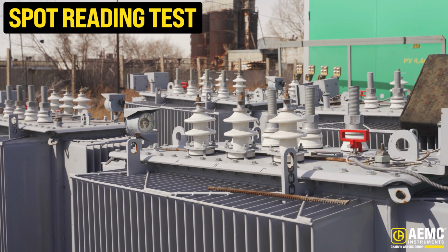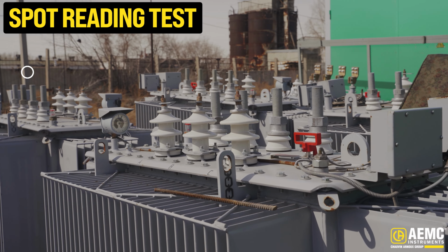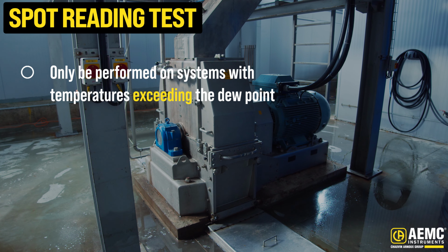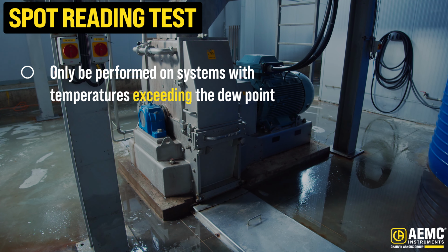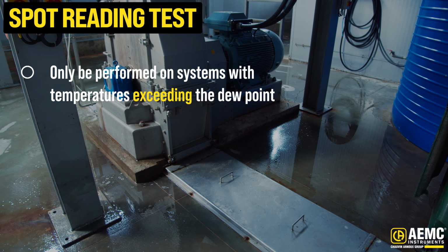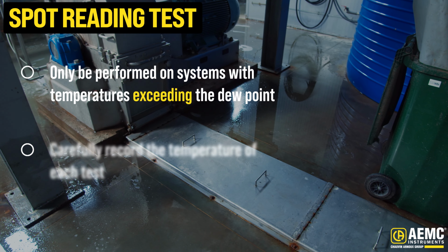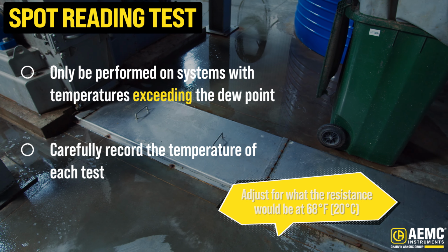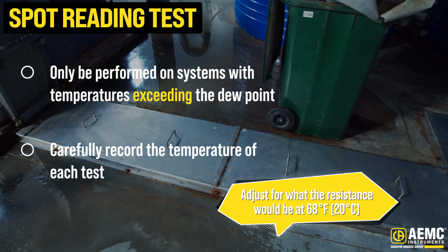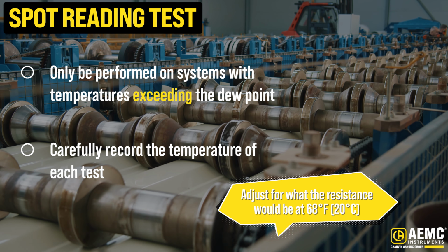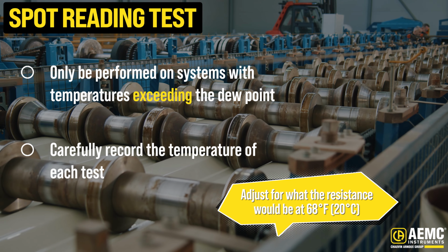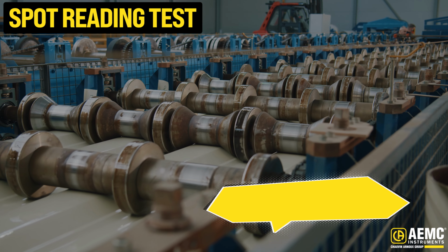To ensure your results are valid, spot testing should ideally only be performed on systems with temperatures exceeding the dew point. If tests are performed at different temperatures, carefully record the temperature of each test and apply the appropriate correction to determine what the resistance would be if the test were performed at 68 degrees Fahrenheit or 20 degrees Celsius.